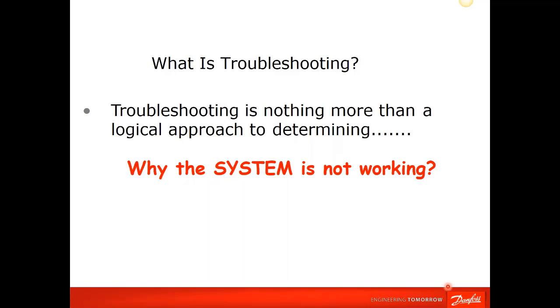So how I started out was troubleshooting mostly something very simple, something that's overlooked. A miswire, a loose wire, something not being physically right. So we're just going to take a logical approach here and eliminate things one by one to make sure that everything is right before we start saying the drive is faulty and wanting to replace things.